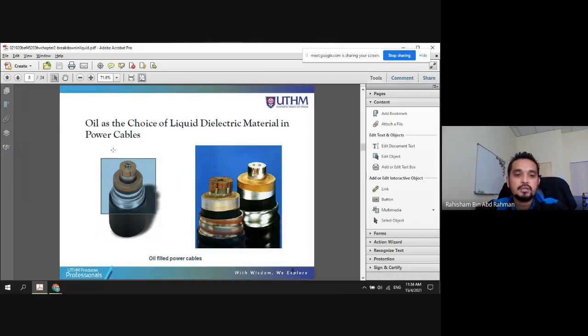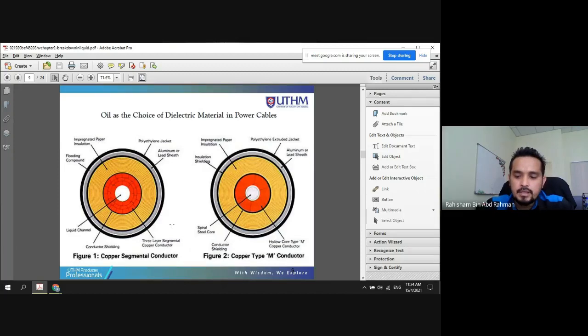We can use gas, yes, we can actually use gas, no problem - we can use normal air, no problem. But we will not have the enhanced capability of dielectric strength; it's not as high as this combination of solid and liquid. This is what we call combinations: solid - this is paper, solid insulation, we have silicon rubber - and we have liquid as well, liquid within the insulated paper, to enhance or improve the dielectric strength. Okay, power cable.